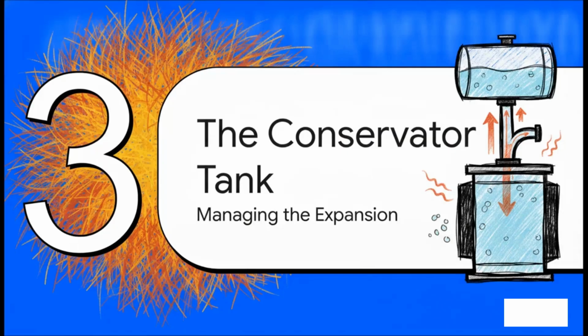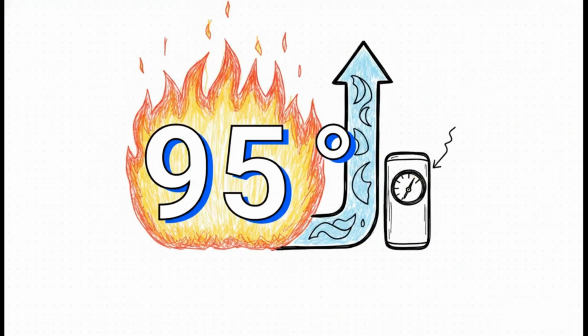Let's look at the conservator tank's role in managing that expansion. Because the main tank is already totally full, this expanding hot fluid desperately needs a safe escape route. At 95 degrees Celsius, which represents the absolute maximum stress our transformer is under, that extra volume of oil is actively pushed up through a connecting pipe into the conservator tank above. If you were standing right next to it, checking out the physical gauge on the side of that top tank, you'd actually see the needle moving upward in real time.